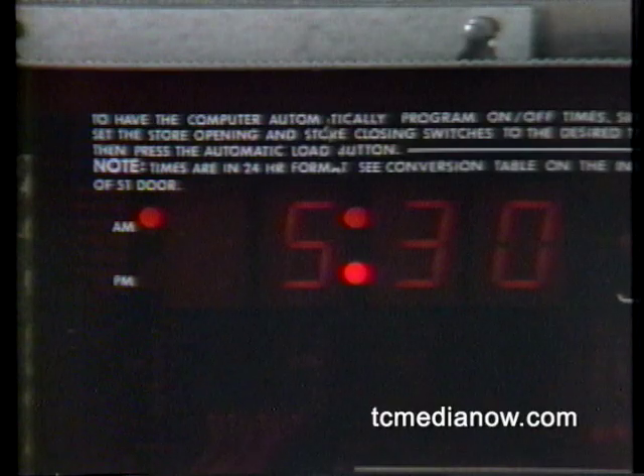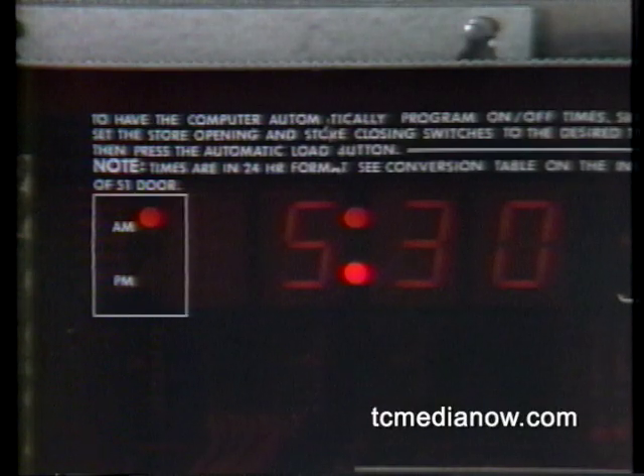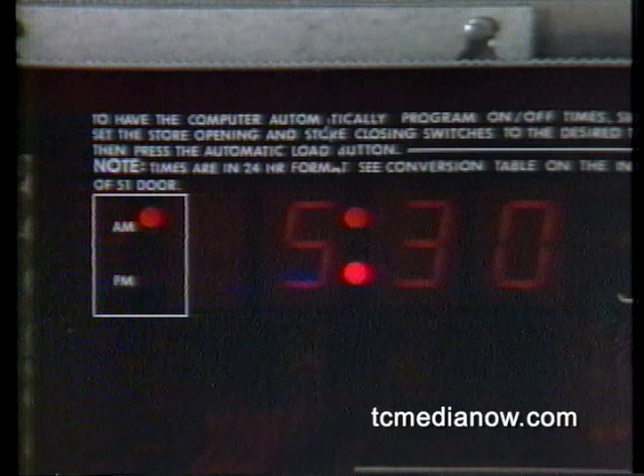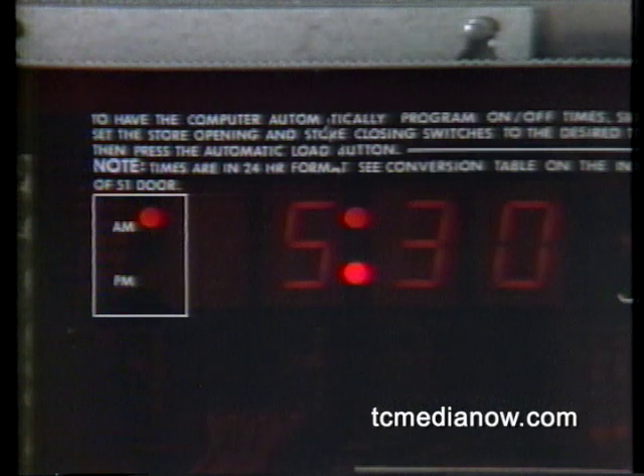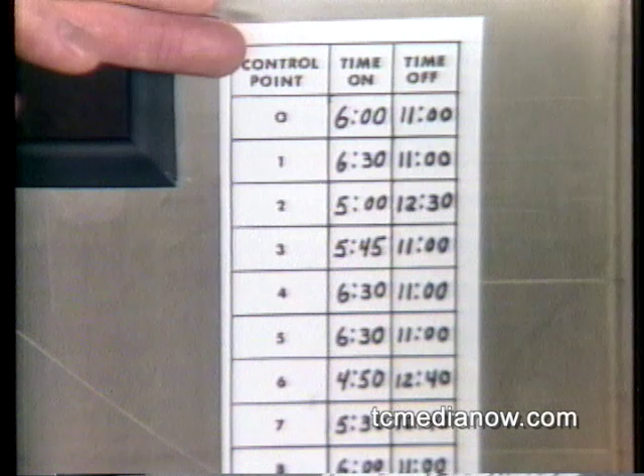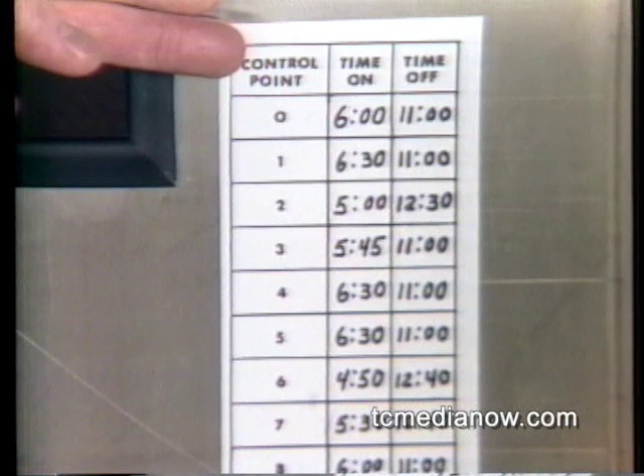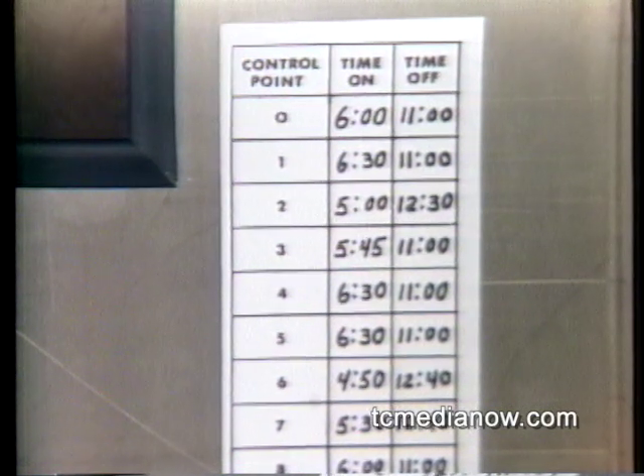Be sure to check the status of the AM/PM indicator when reviewing programmed time cues. Remember, the most common programming error is to enter AM when PM is intended, or vice versa. Whenever you make changes to the auto load program, be sure to note the time cues you've set on the time cue record chart found on the inside of the clock panel cover. This record will be a big help to you if you should ever need to correct an entry or duplicate a custom program.